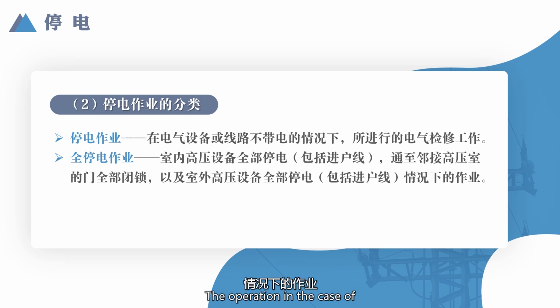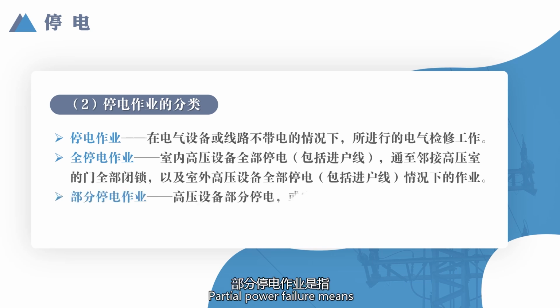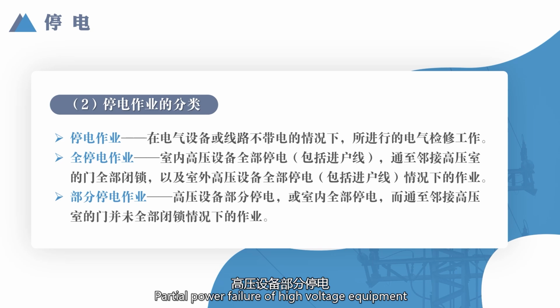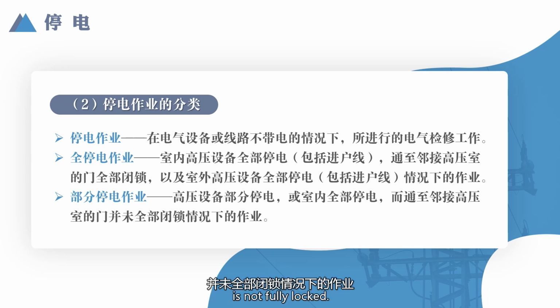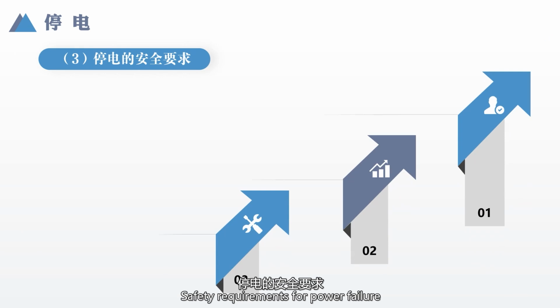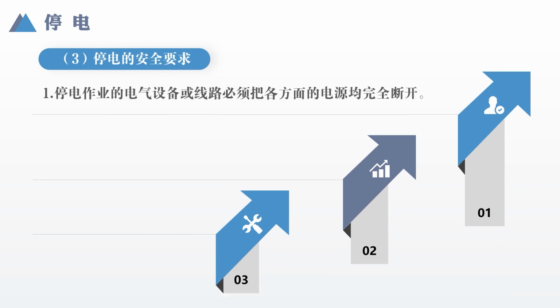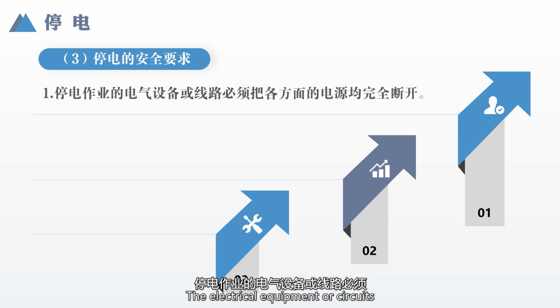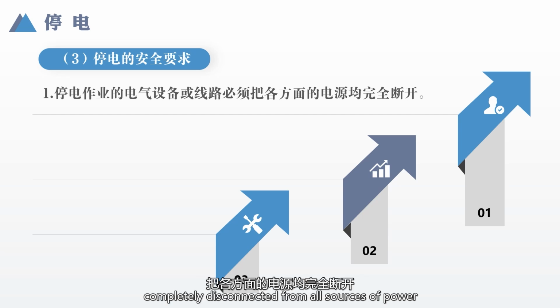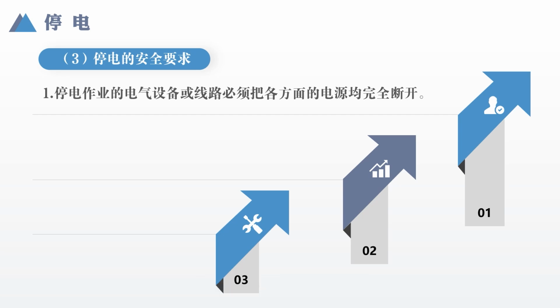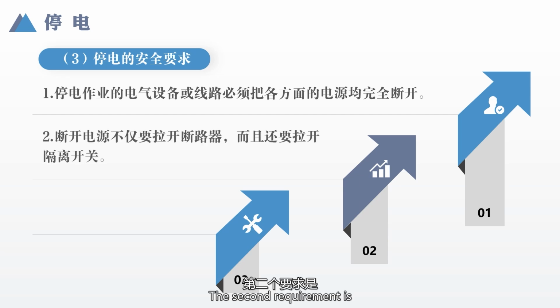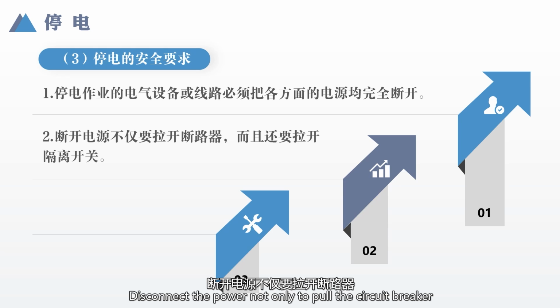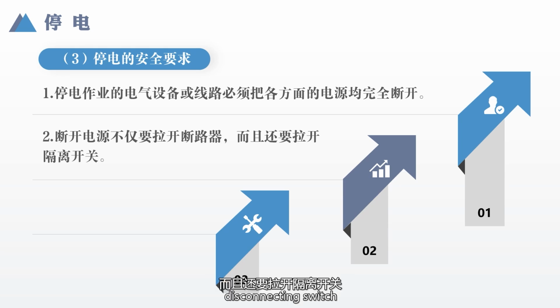inlet lines. The operation in the case of partial power failure means partial power failure of high voltage equipment or total power failure of indoor equipment, and the door to the neighboring high voltage room is not fully locked. Safety requirements for power failure. The first requirement is the electrical equipment or circuits to be de-energized must be completely disconnected from all sources of power. Ensure safety. The second requirement is to disconnect the power, not only pulling the circuit breaker but also the disconnecting switch.